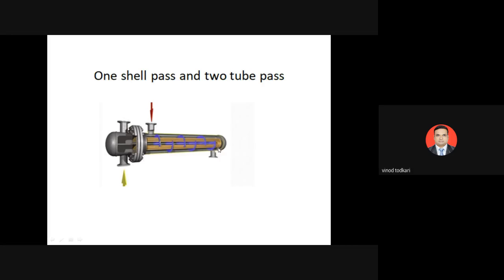Looking at the cut-section view: the tube fluid enters at the left, moves to the right, then back to the left, so there are two tube passes. The shell inlet and outlet are on opposite sides with the fluid flowing over the baffles, giving one shell pass. This is a one shell pass and two tube pass arrangement.